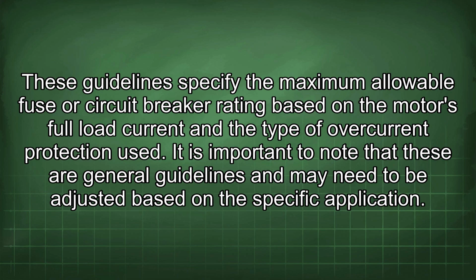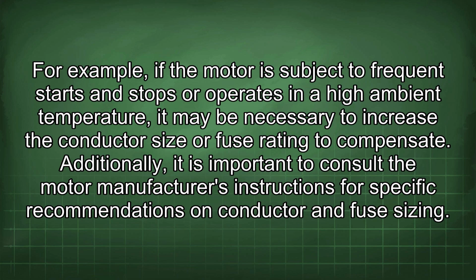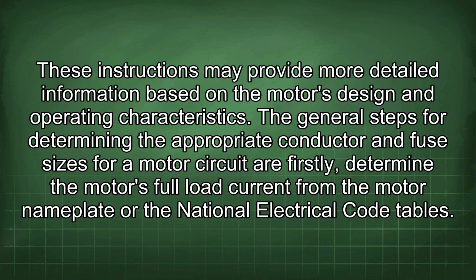It is important to note that these are general guidelines and may need to be adjusted based on the specific application. For example, if the motor is subject to frequent starts and stops or operates in a high ambient temperature, it may be necessary to increase the conductor size or fuse rating to compensate. Additionally, it is important to consult the motor manufacturer's instructions for specific recommendations on conductor and fuse sizing. These instructions may provide more detailed information based on the motor's design and operating characteristics.